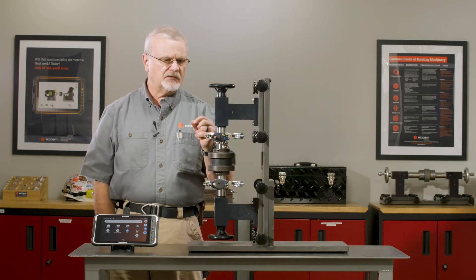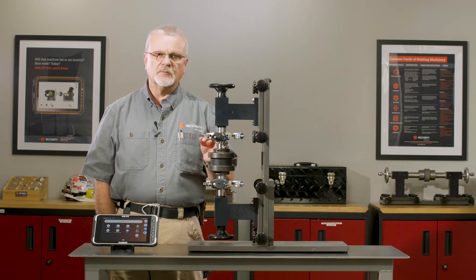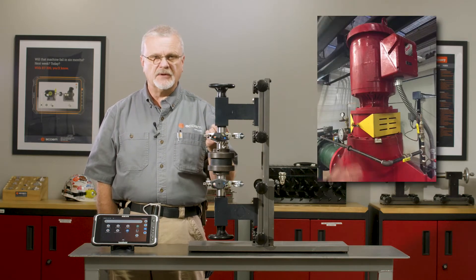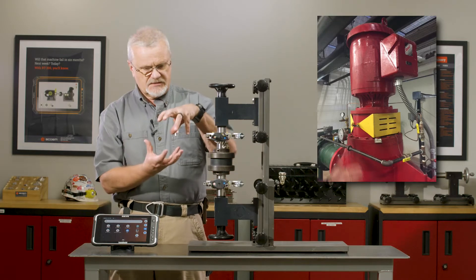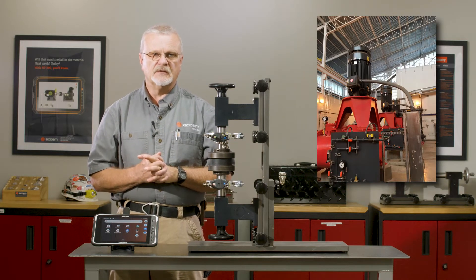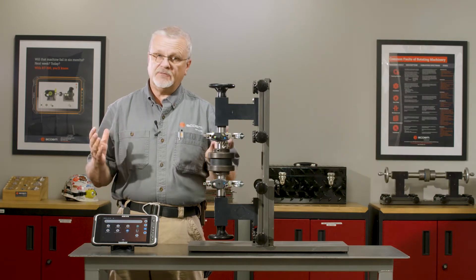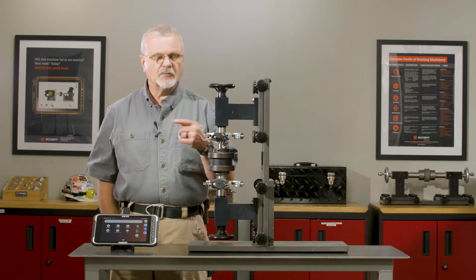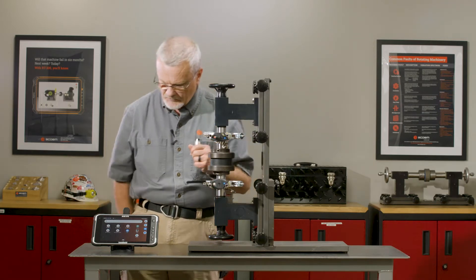Just to preface this: a lot of people think that vertical machines don't need an alignment check because that C-face flange has a rabbet joint that's machined around it, so that the C-face flange bolts into the top of the pump assembly. But I have seen them out of alignment due to machining errors, dirt buildup, or whatever. So we're going to go through this process and I think you'll see how it works.